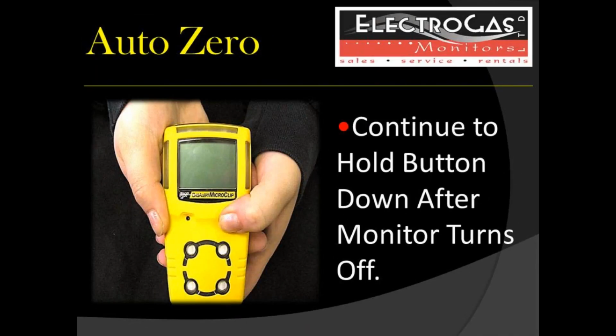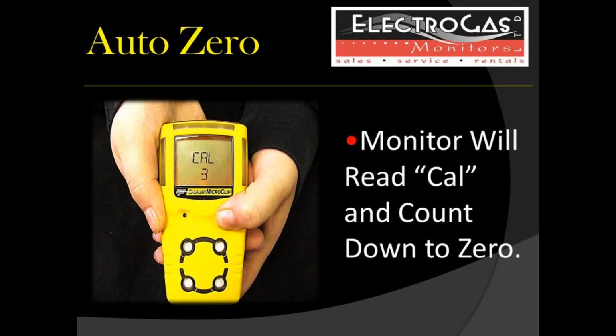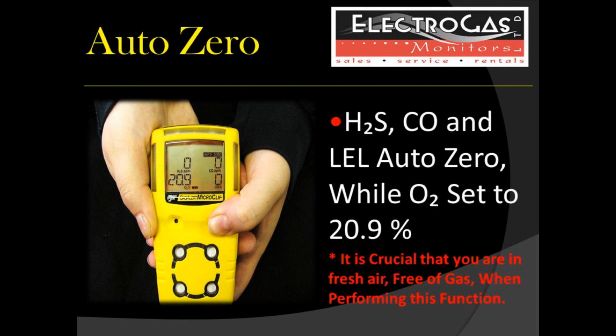Continue holding the button down after the monitor has turned off. Your monitor will then display Cal and count down from 3 to 0. All 4 sensors will then be displayed. Oxygen will once again be set to 20.9 and all other sensors will set to 0.